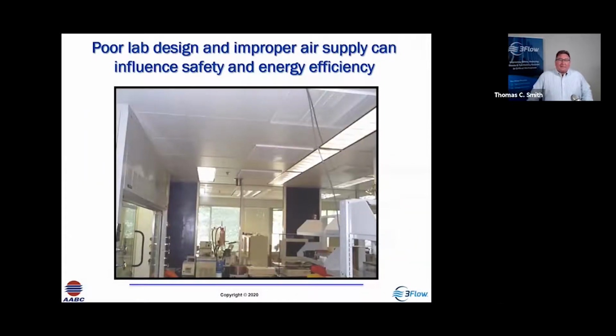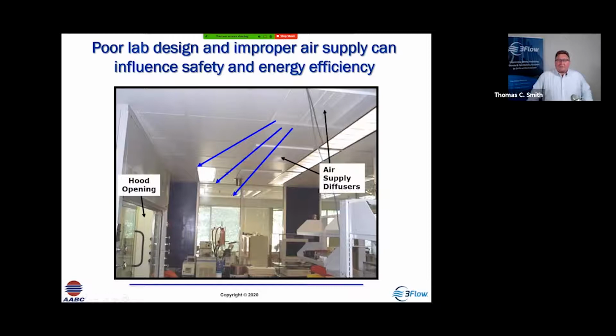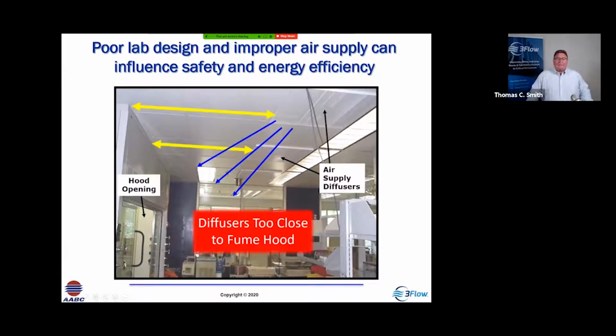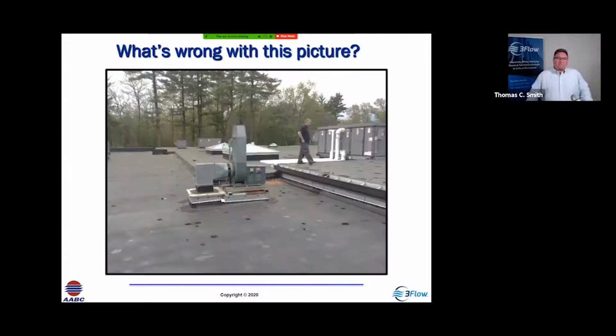Now we also look into a lab. If you look into this space, what do we see? We've got a hood over here on the left. We've got supply diffusers. They look like good diffusers, but if we count the ceiling tiles, which are 2x2, we see that it's only about 2.5, maybe 3 feet from the hood. Diffusers should be at least 5 feet from the hood. If they're too close, we're going to get cross drafts that create turbulence, and that can also short circuit air directly to the hood, so we're not getting the utility out of that heated and cooled air in the lab space. It's being short circuited and possibly causing problems with hood containment. So that's another factor we really need to look at: diffusers should be at least 5 feet from the plane of the hood.